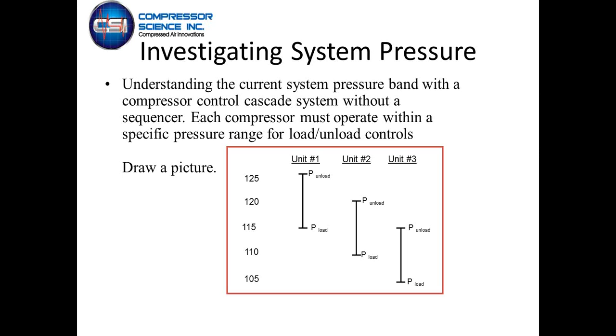So, you know, the unit number 1 is going to unload at 125 psi, load at 115. Unit 2 is going to come on, unload at 120 psi, load at 110. And your third unit in the circuit is going to unload at 115 and load at 105 psi. So really, you're operating within a 20-pound pressure band there in order to have the compressors come on and off, hopefully within a period of time where they're not going to stay loaded that long before they actually unload and shut down. So it's not necessarily the most efficient way to run.